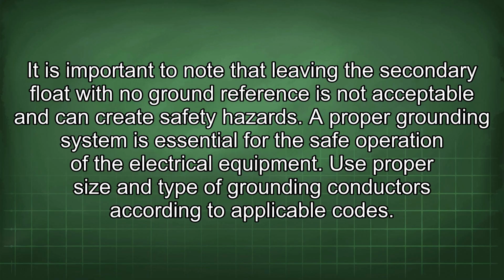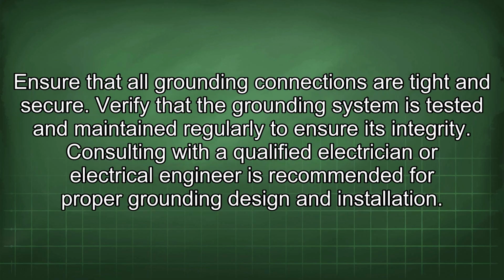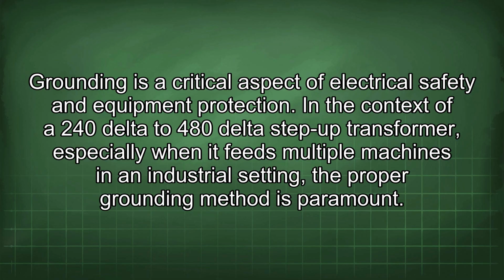Use proper size and type of grounding conductors according to applicable codes. Ensure that all grounding connections are tight and secure. Verify that the grounding system is tested and maintained regularly to ensure its integrity. Consulting with a qualified electrician or electrical engineer is recommended for proper grounding design and installation. Grounding is a critical aspect of electrical safety and equipment protection.